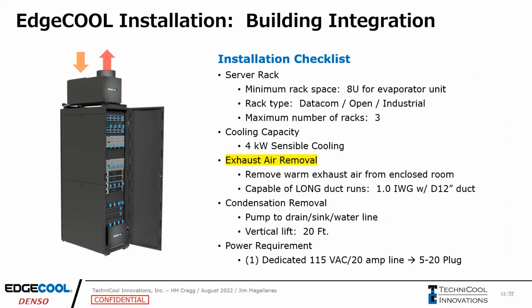So here's the checklist on how you integrate this unit into your customer's building. You want to check the server rack and make sure there's a minimum of 8 U of space for the evaporator. What type of rack is it: datacom, open, industrial. Make sure we're cooling a maximum of 3 racks, with 4 kilowatts of sensible cooling, exhaust air. We're removing the warm exhaust air from the enclosed room. Our system's capable of long duct runs. We have 1 inch of water gauge at a 12-inch duct.